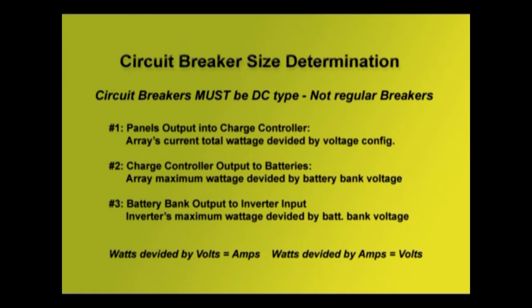Number 2, the charge controller's output, going from the output of the charge controller into the batteries to charge the batteries. We're going to put a breaker there, and that is the array's maximum wattage divided by the battery bank voltage. That's going to give us the maximum current that that charge controller is going to ever deliver to the batteries. And like I say, it's a little bit safer to run a little bit less of a circuit breaker capacity there if you need to. 1.5 is ideal. You can come down a little bit. The output of the charge controller is protected inside the circuit itself, so you get a little bit of extra protection there to begin with.